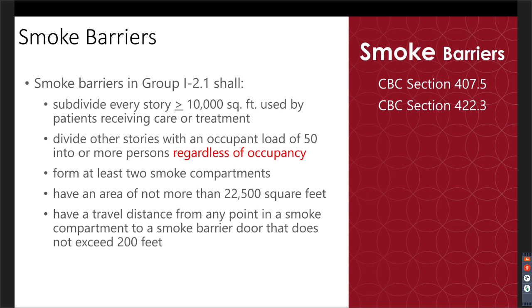we have a smoke compartment for any story greater than 10,000 square feet used by patients receiving care or treatment, and for other stories with an occupant load of 50 or more. We have to switch that language around a little bit there, regardless of the occupancy. So those stories would need smoke compartments for relocation purposes. And then you have to have at least 2 smoke compartments in these facilities. And those smoke compartments cannot exceed 22,500 square feet. And the travel distance from any point in the smoke compartment to a smoke barrier door cannot exceed 200 feet.